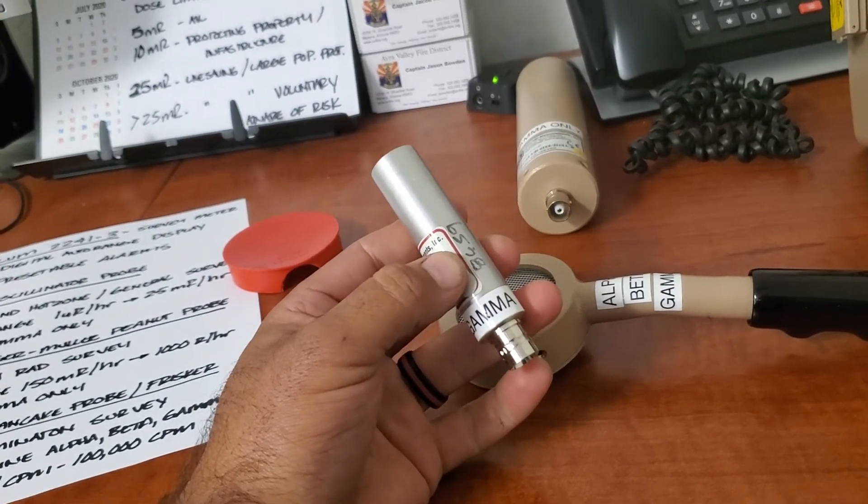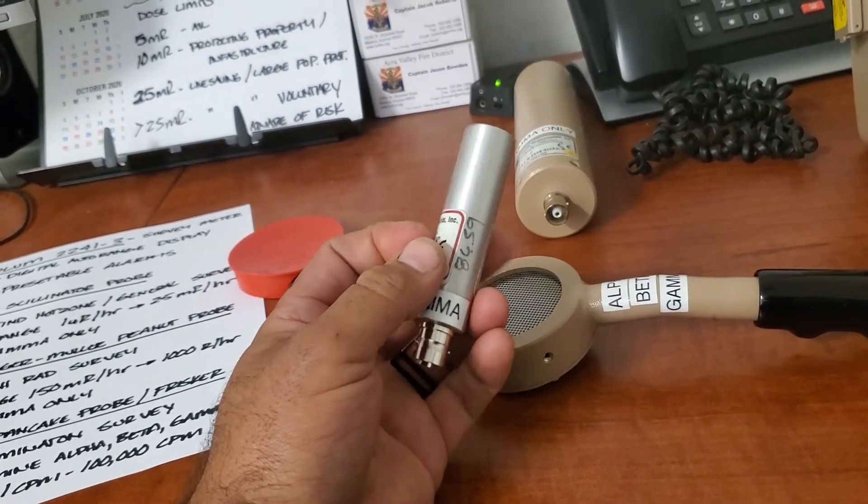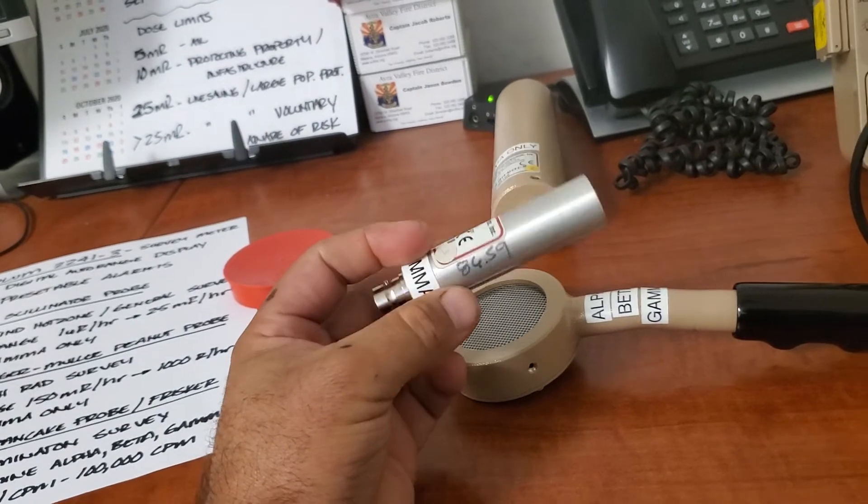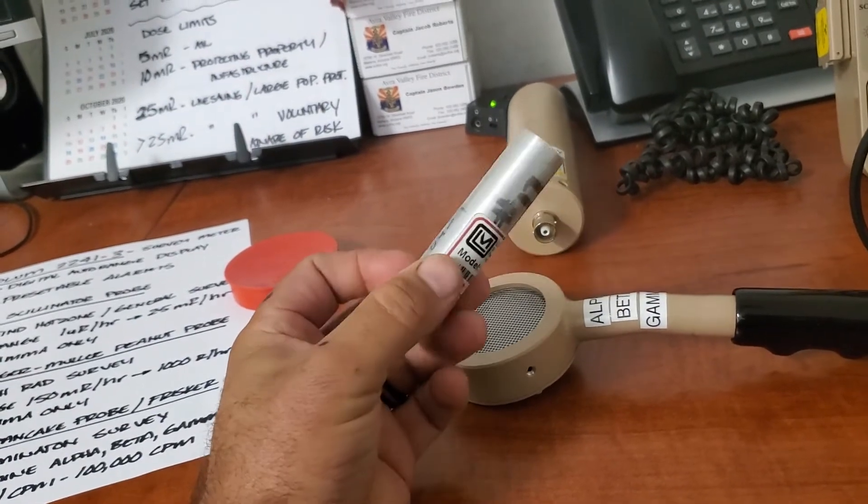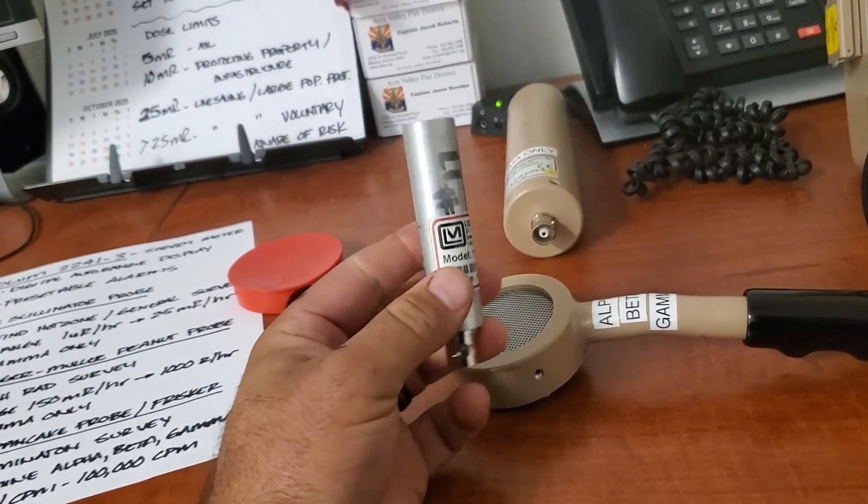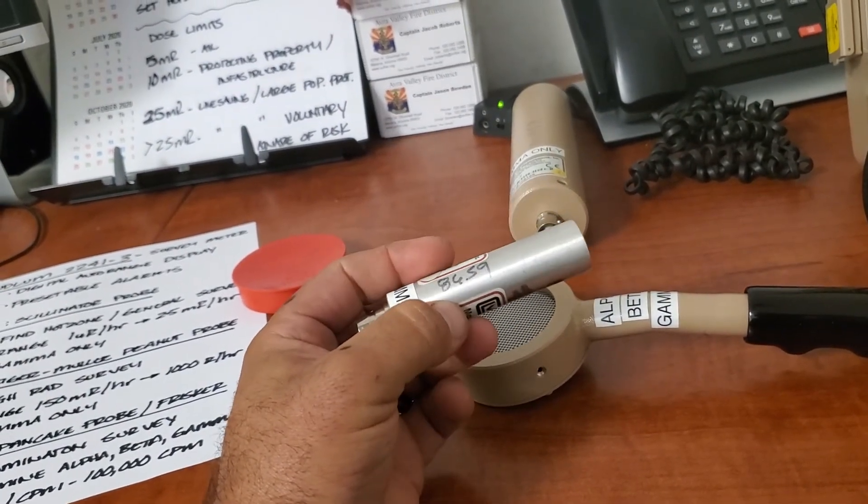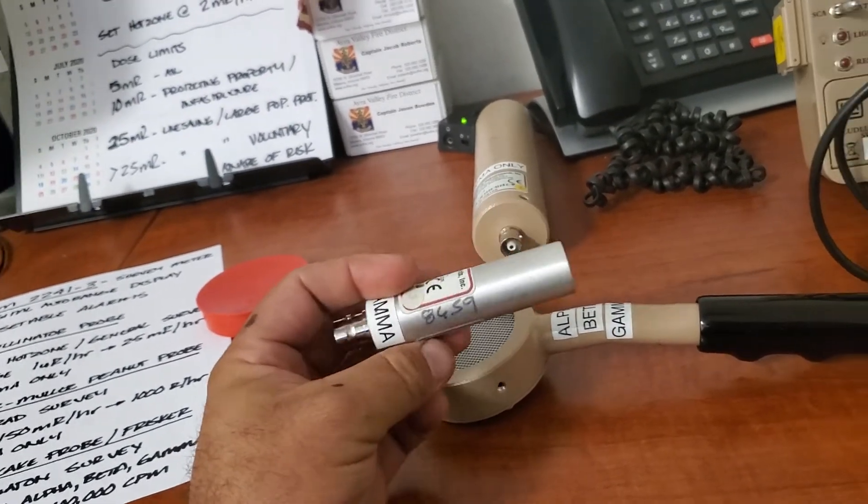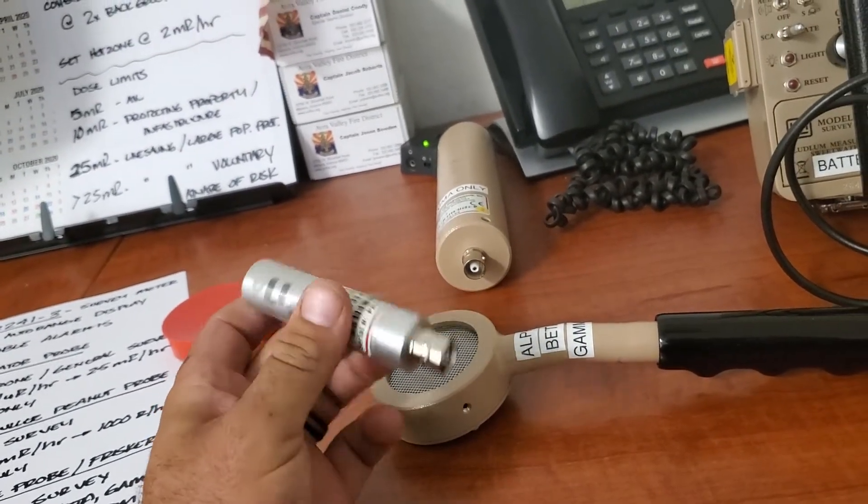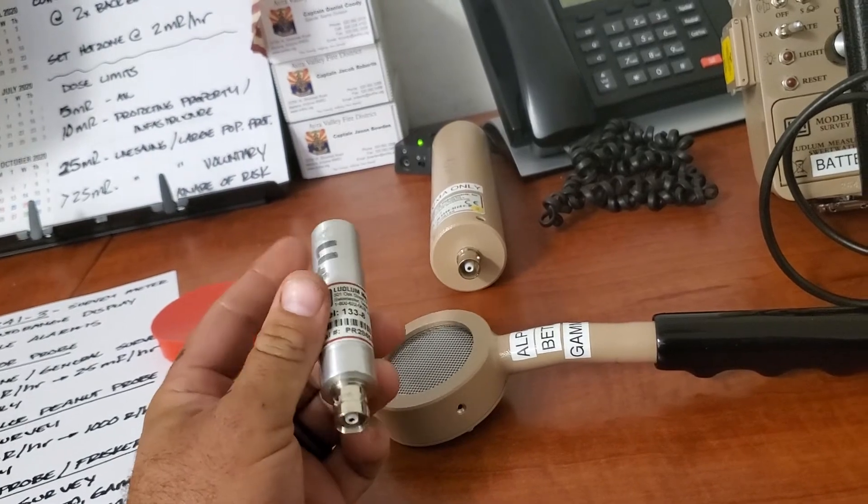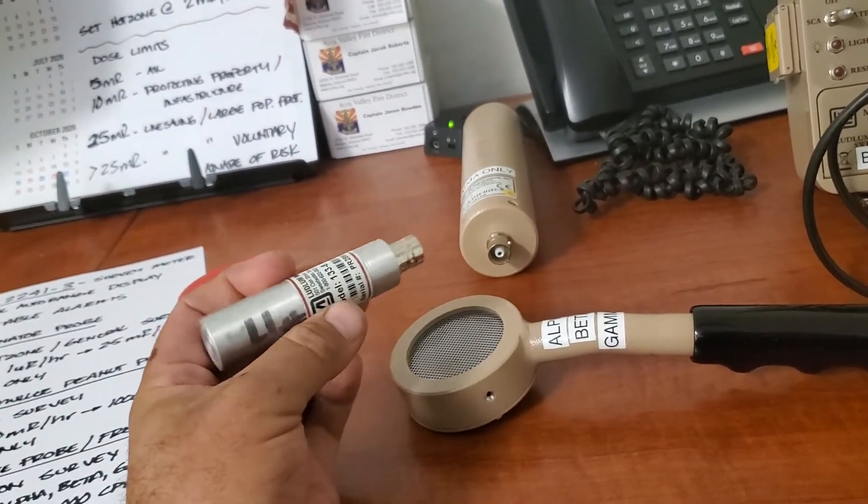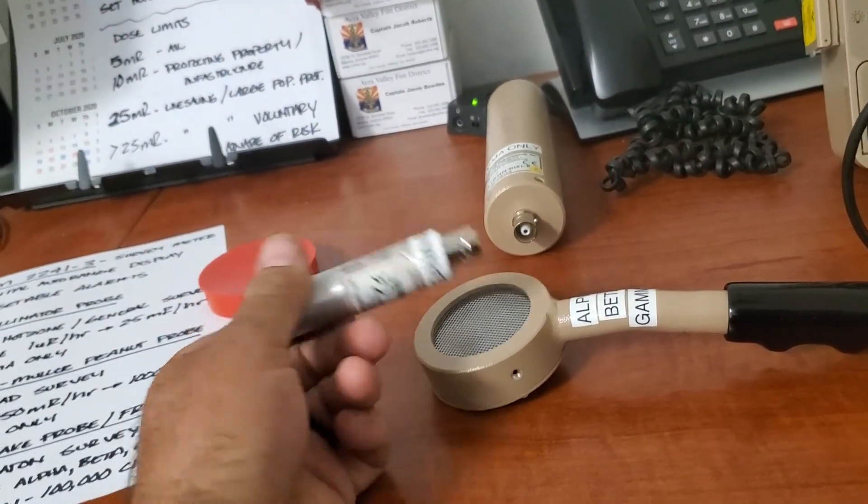Like I said, I went ahead and labeled it for you. This is the 133-8 Geiger Mueller, also known as the peanut probe. This is for very high radiation surveys. We're talking 150 millirem an hour to 1000 R per hour. Yeah, this puppy, if you're using it, you're dealing with something that's significantly hot, and you're not going to want to be around it for too long.